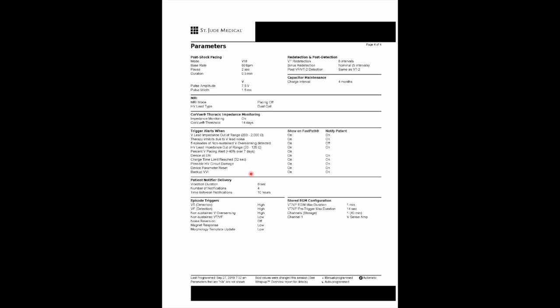If you recall, or if you've been in the industry for a while, or in the space for a while, there have been recalls or advisory devices. And one of the things that we were doing when that first advisory came out was that we were extending the vibration duration, we were extending how many notifications, and we were shortening the time between the notifications. That way, if there was a premature failure, we really wanted to make sure that patient was going to feel it. The downside of this vibratory alert on this device is that if a patient does not know that it can vibrate, it can absolutely scare the heck out of them.